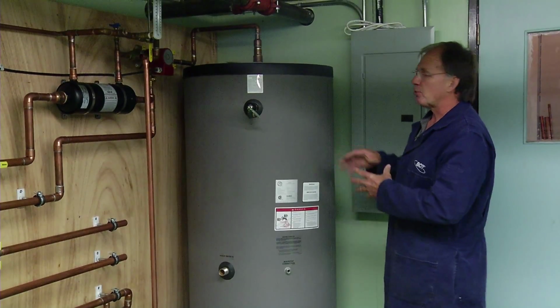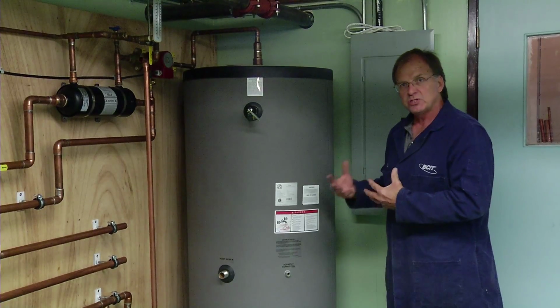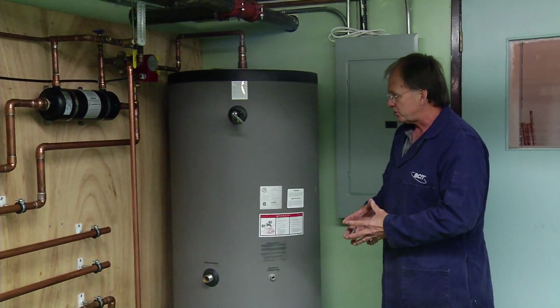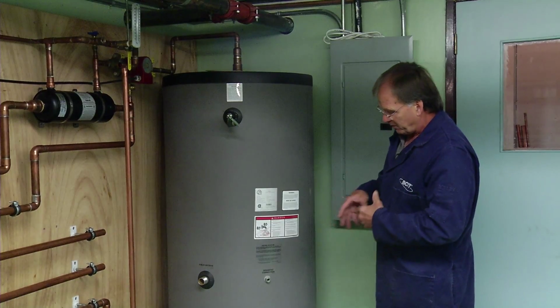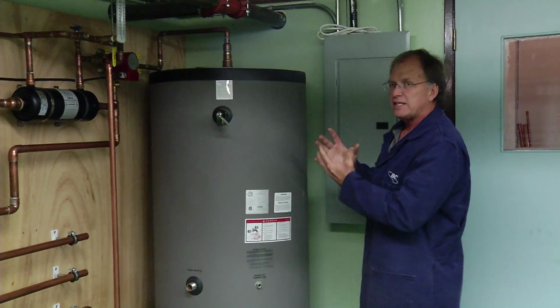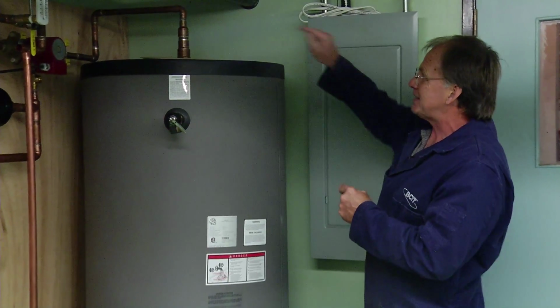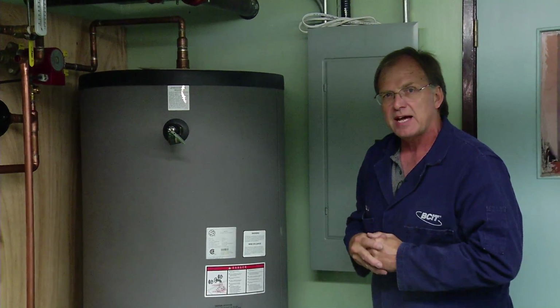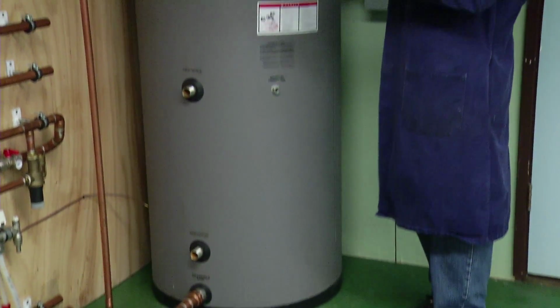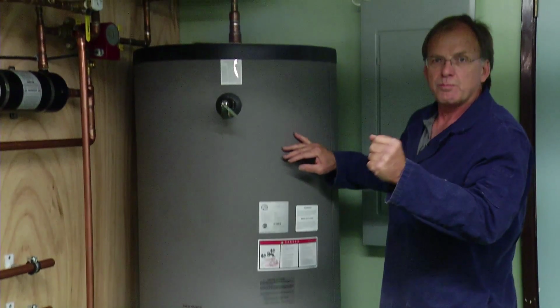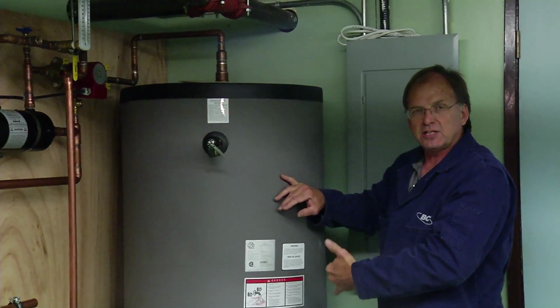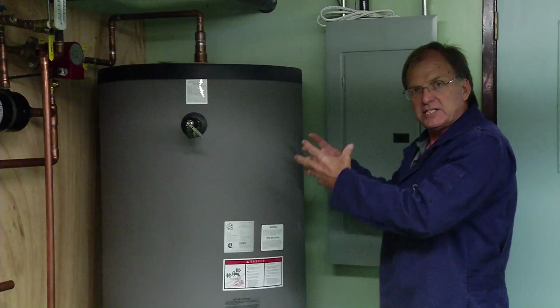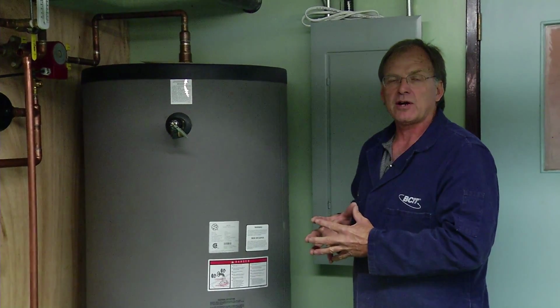Another piece of technology that gives us energy efficiency is an indirect hot water tank. This tank's purpose is to store hot water for use in the domestic load, in other words, your showers and your kitchen. The energy efficiency comes because this is a well-insulated tank, but primarily it doesn't have a vent because it doesn't have a gas burner on the bottom. This tank receives its energy from the boiler. The boiler water is fed to the coil in here. The coil releases its heat and heats up the domestic water.